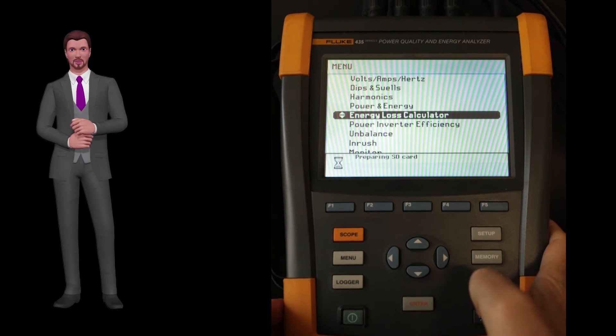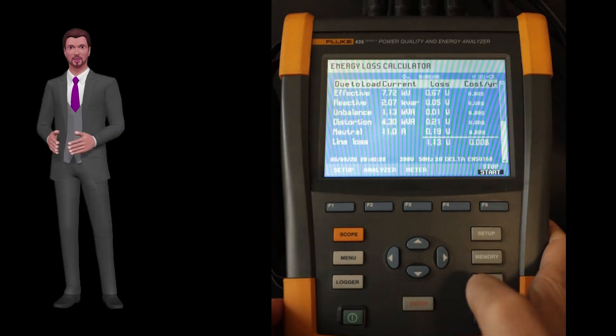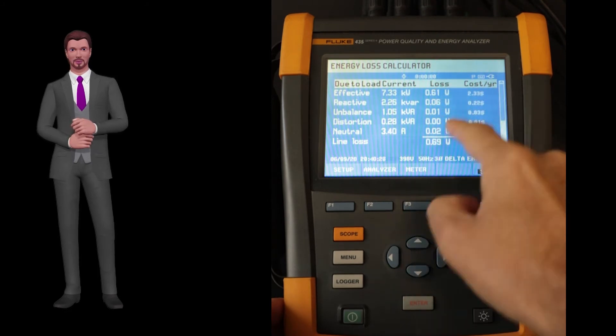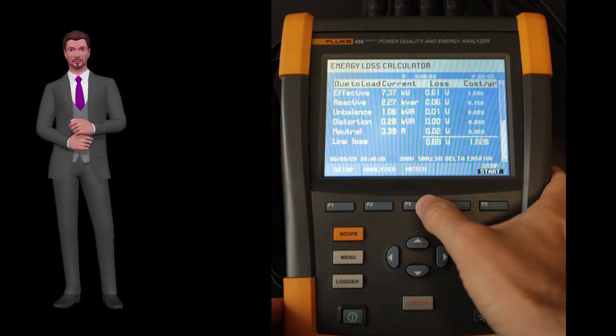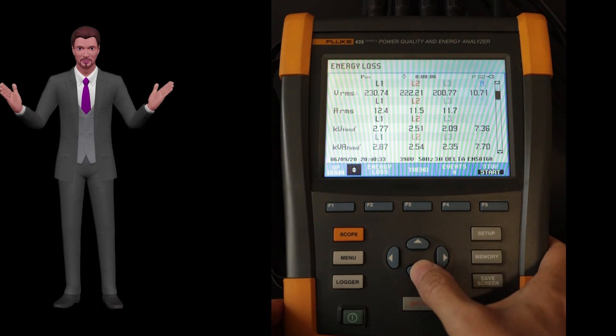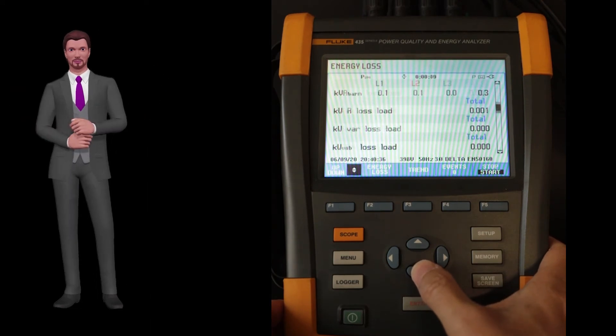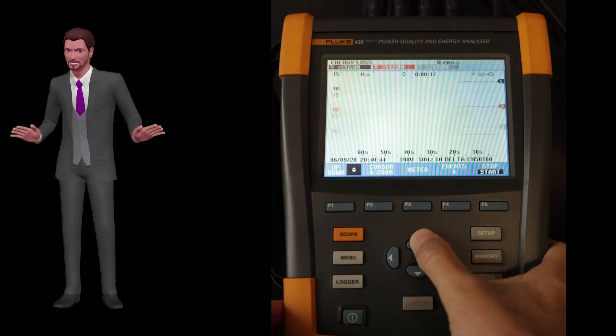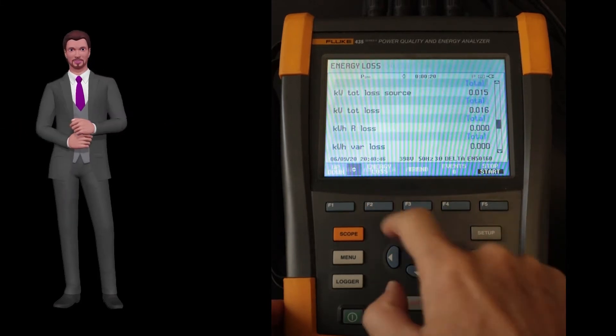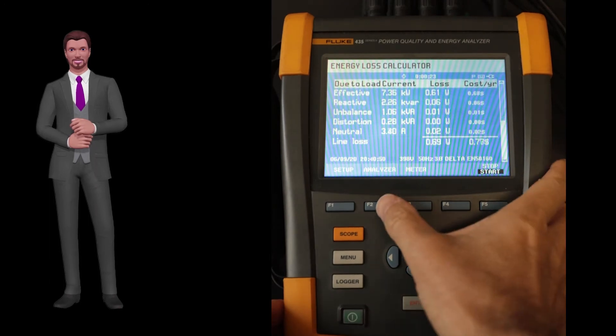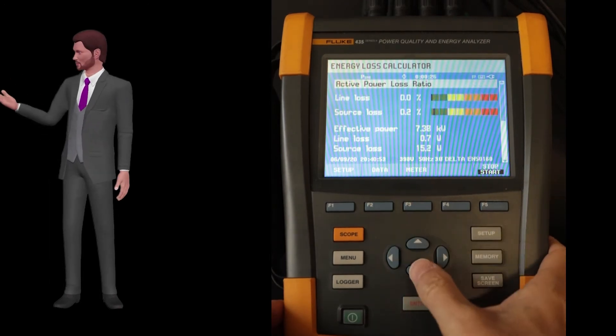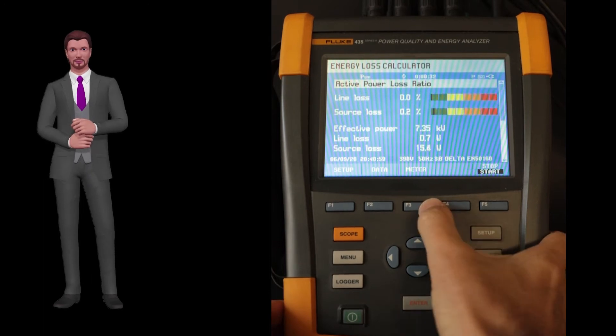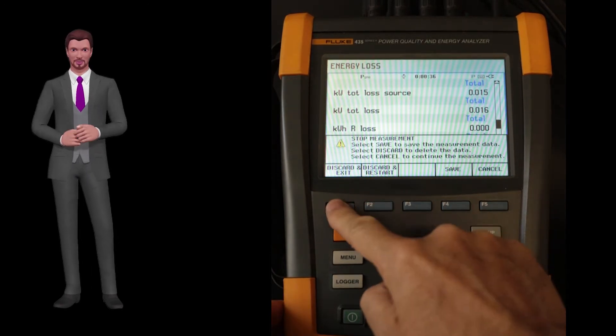Then comes the energy loss calculator function, which allows us to see and record the active, reactive, harmonic, and unbalanced powers already mentioned, but also the losses that occur in the distribution cables associated with those powers. We get that information in watts but also their economic quantification. If you have reactive, harmonic, or unbalanced problems, this function is very important in order to decide and justify, for example, the installation of a capacitor bank, a harmonic filter, or simply balancing the loads.